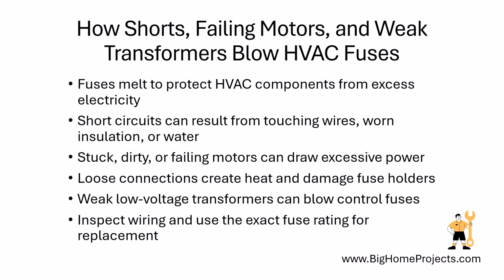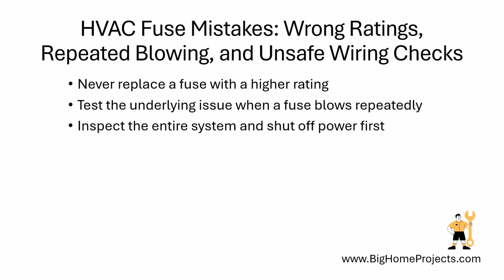Replace a blown fuse only once with the exact same type and rating, because a new fuse can reveal a problem but cannot repair it. A common mistake is replacing the fuse with a larger one, but that can allow wires to overheat, so always use the specified rating. Another mistake is assuming the fuse itself is the main problem.